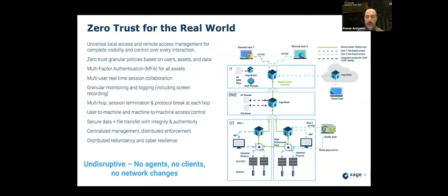Xage enforcement filter, which is deployed in the lower parts of the architecture, works with the fabric to dynamically control access down to individual PLCs. Unlike other access solutions, Xage is able to control access down to individual PLC level. So an account can be injected in a workstation, and then the Xage enforcement point is orchestrated to restrict access down to a specific PLC only for the duration of the time that's required for the work to be performed.